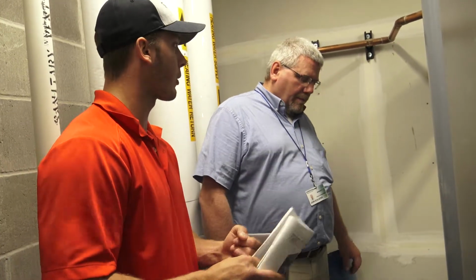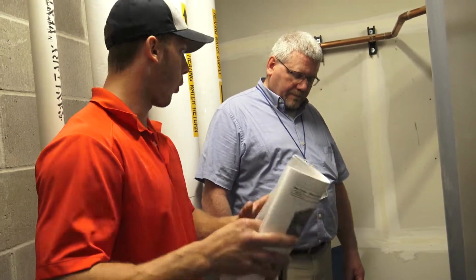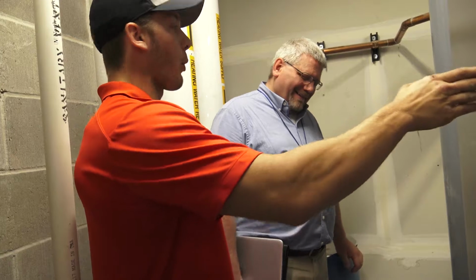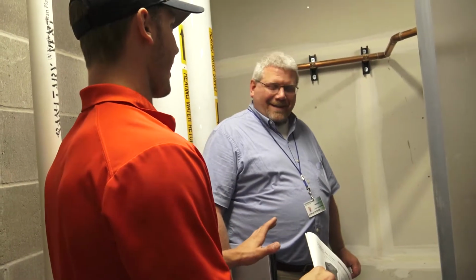I do not recommend, when they touch the gas valves, that they do anything but use the throttle screw. Don't try to mess with the bias screw. You'll see people try to pinpoint their combustion. Hey, well, it's 0.3 off. 0.3 is okay. Yeah. Okay.